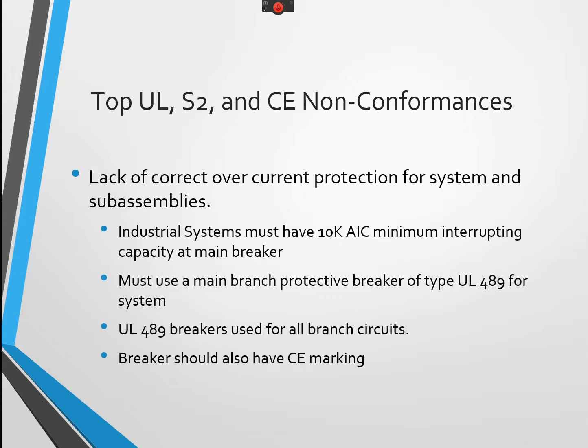Lack of overcurrent protection we've talked about. That overcurrent protection must have 10,000 amps interrupt. You have to use a UL 489 breaker for North America for your main and branch circuits, and breakers should also have CE labeling on them.